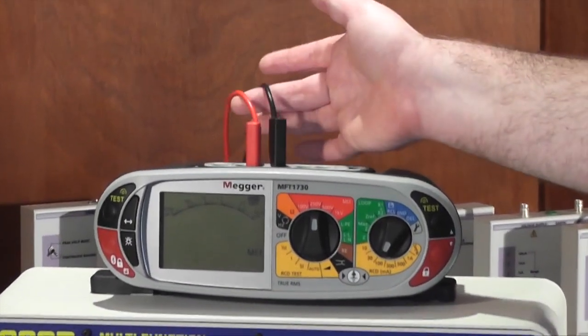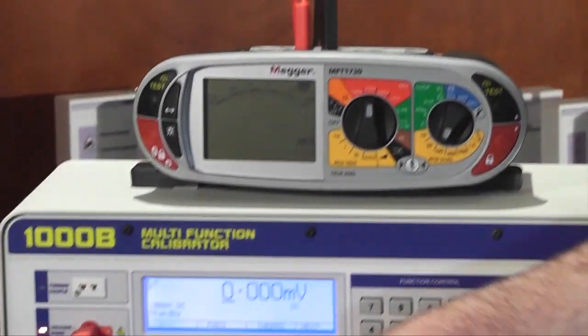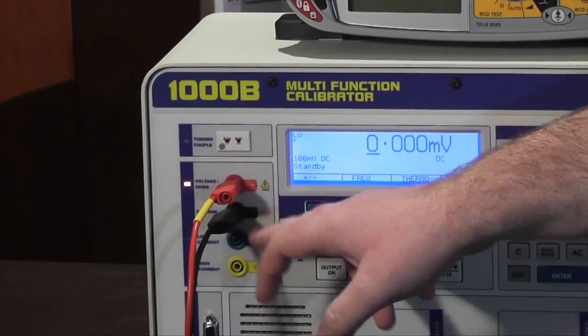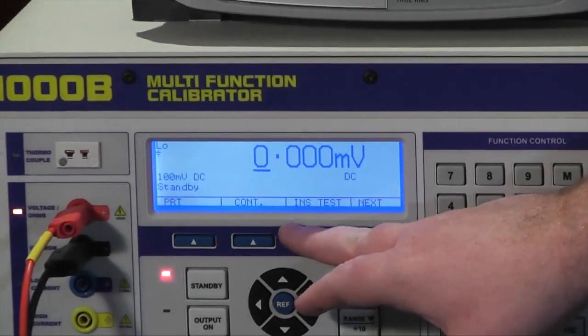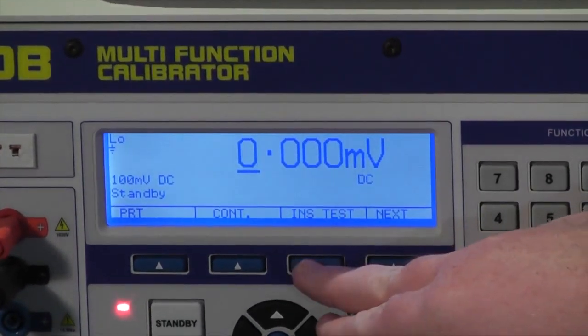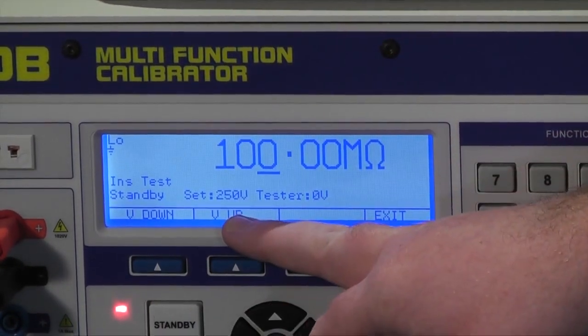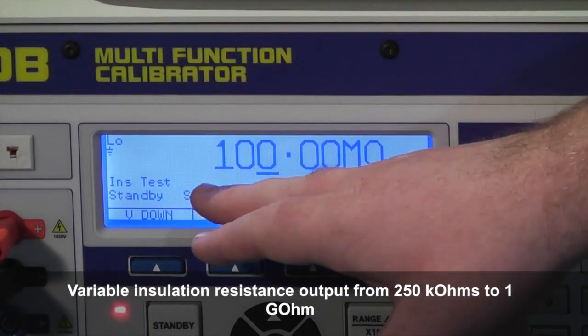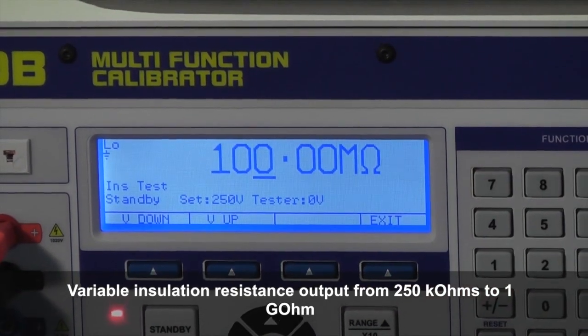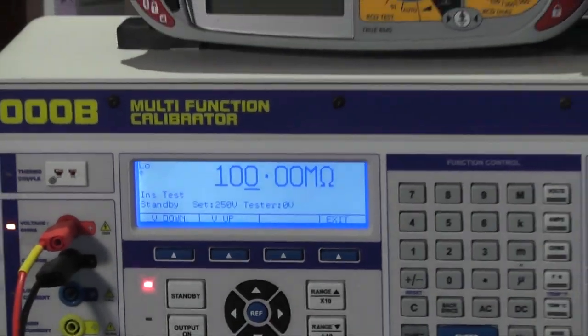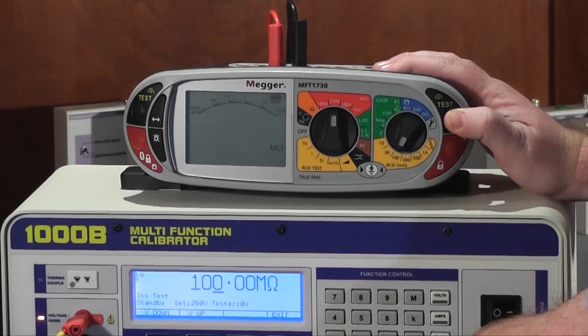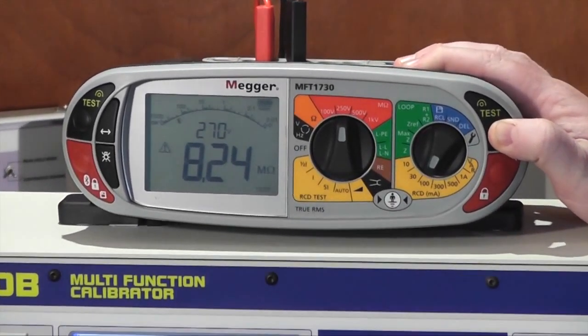Simply connect your insulation tester to the terminals on the 1000 series, select the insulation test function, select your voltage, in this case 250 volts, and set the required output, in this case 100 mega ohms. Then simply press test on your tester and press output on the 1000 series.